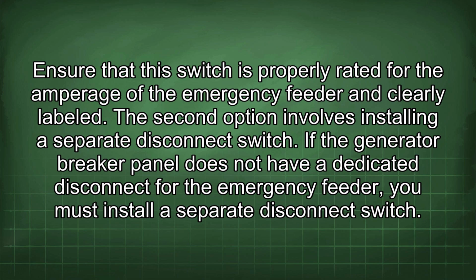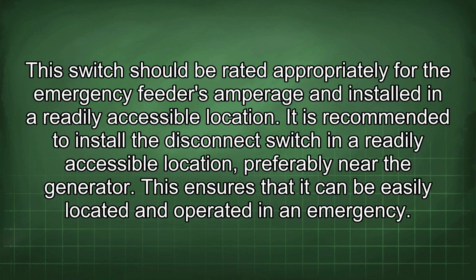The second option involves installing a separate disconnect switch. If the generator breaker panel does not have a dedicated disconnect for the emergency feeder, you must install a separate disconnect switch. This switch should be rated appropriately for the emergency feeder's amperage and installed in a readily accessible location.